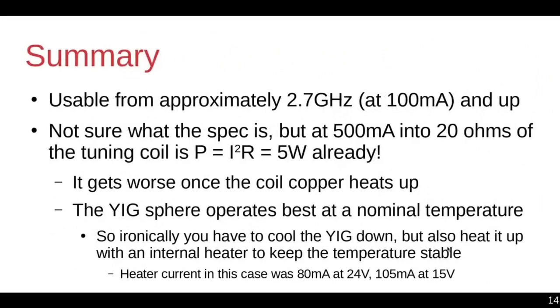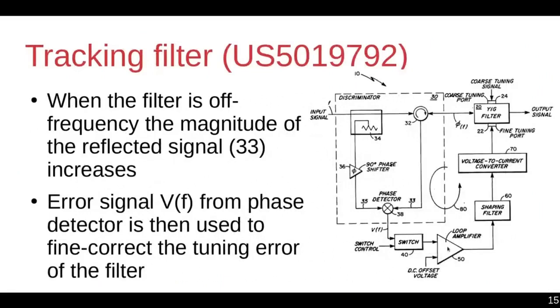You can also use filters in a closed-loop control. As an example: if the YIG filter is adjusted to a different frequency than what you want to pass from input to output, the power gets reflected. Because of a circulator, that power goes down to a port where it gets compared, produces an error signal, and the error signal tunes the filter back into position — so the reflected power gets minimized. One of the key points of this talk will be this driver circuitry, which consists of a tuning signal and a fine-tuning signal.